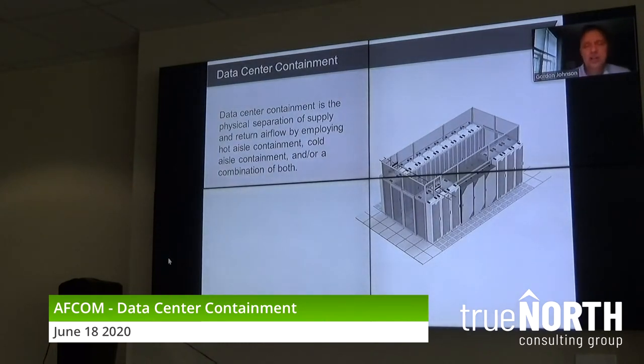What is containment? In its simplest form, containment is separating your cold supply air from your hot return air. We only want one thing to happen in your data center. We want your IT equipment to get cold supply air, and we want that exhaust air from those racks to go nowhere else except back to the cooling unit, maybe a CRAC, CRAH, in-row cooler, or whatever it is. That's where we want that hot air to go. We want to prevent that cold supply air and that hot exhaust air from mixing. And we can do that by deploying either cold aisle containment or hot aisle containment. In a few rare cases, we even do a hybrid design, which is a combination of both. Now we'll get into that a little bit more in just a second.